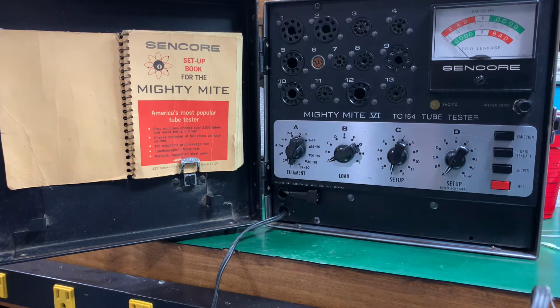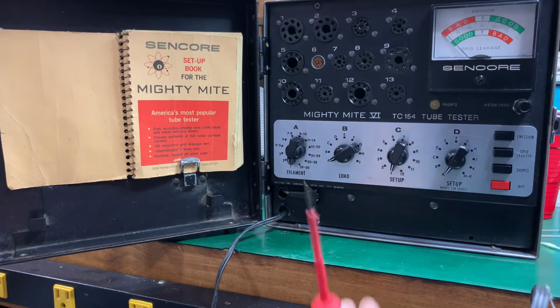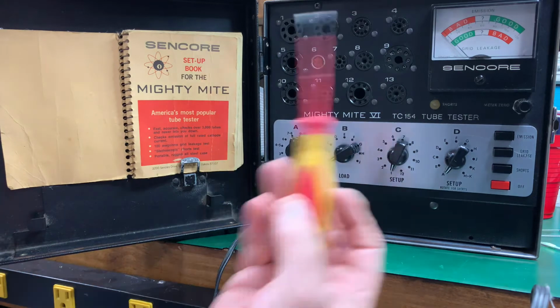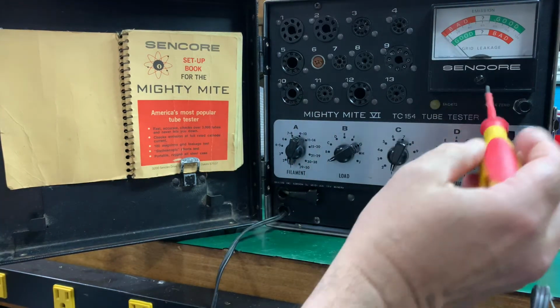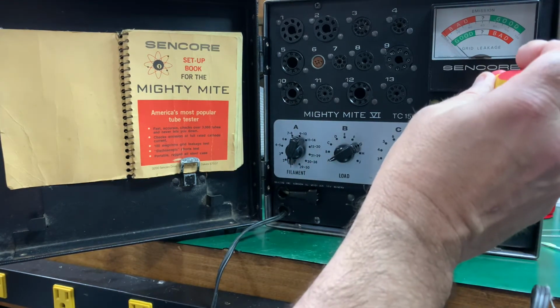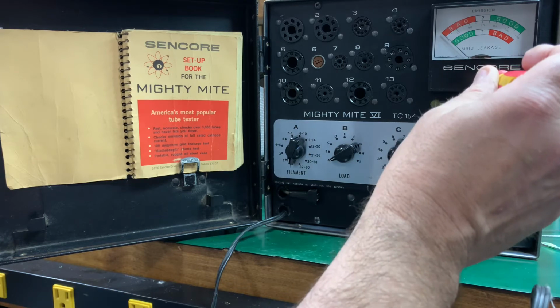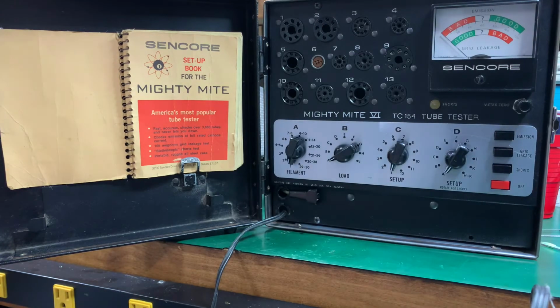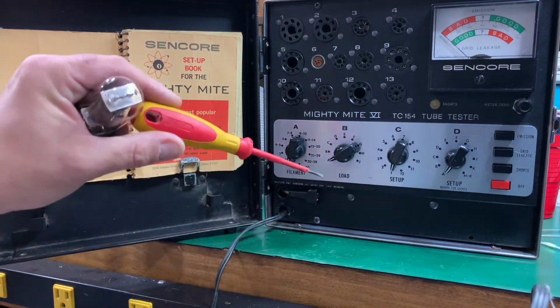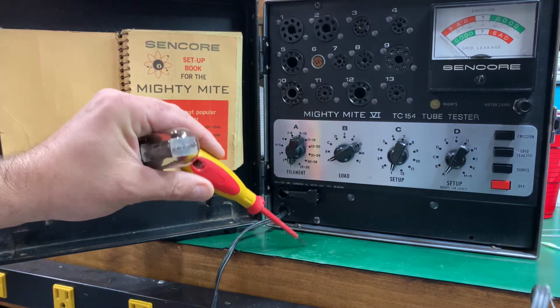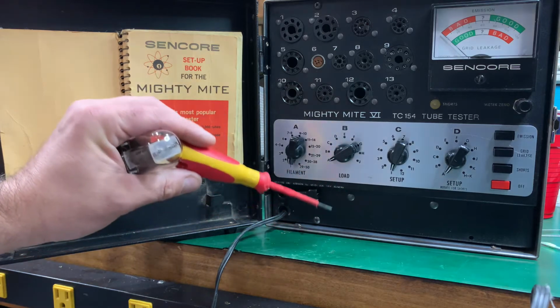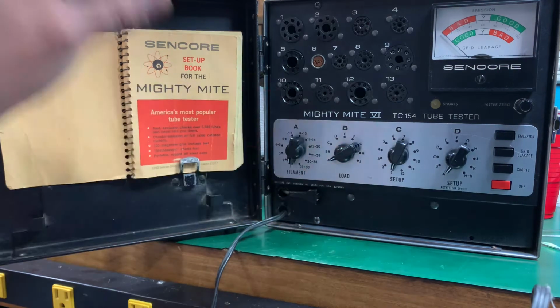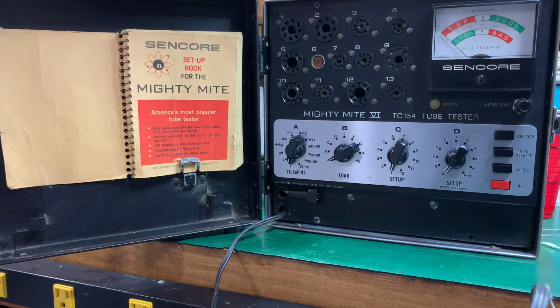So I call this the cold position, where it's plugged in, it's off, all the switches are to the left, or the start position. First thing you do, you look at your meter here. You want to zero it, might get banged around, so I just want to make sure that's on 0. This will not affect the calibration. I did perform a calibration on this. I replaced every component in it that was out of tolerance. So this tester is 100% ready to go.